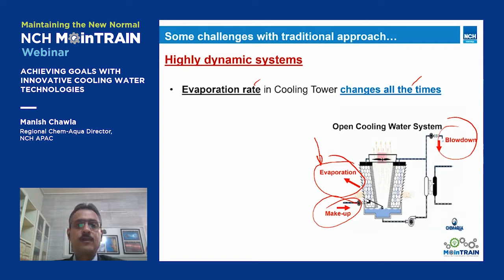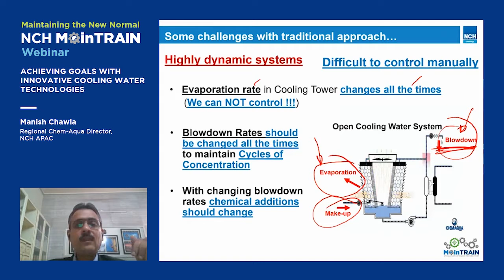Now, if it is changing from morning till night, that means somebody has to sit down there and keep on controlling the blowdown if we want good results. Now, with the changing blowdown, chemical addition has to be changed. So these are highly dynamic systems, very difficult to control manually. Then many of the variables will conflict or compete with each other.